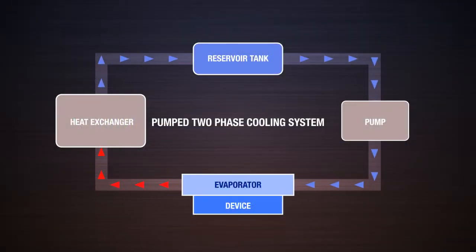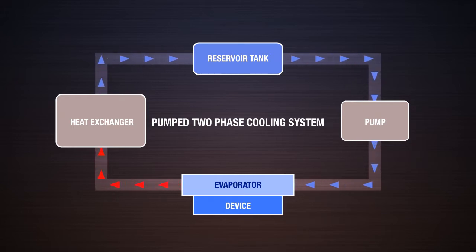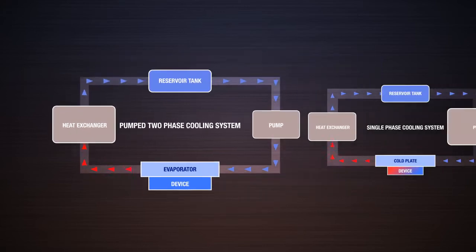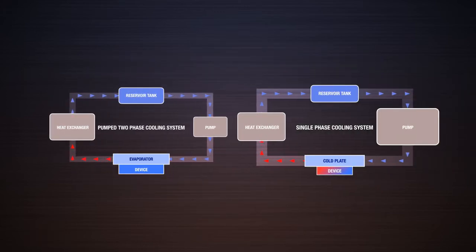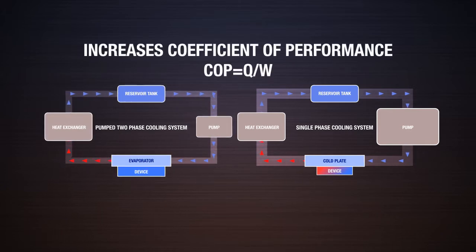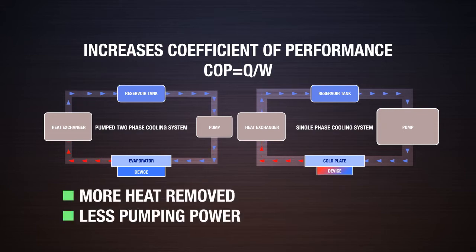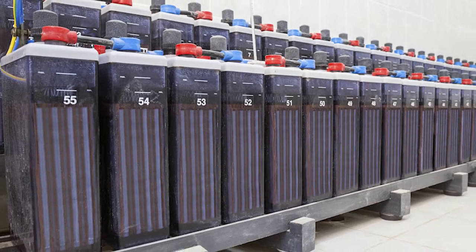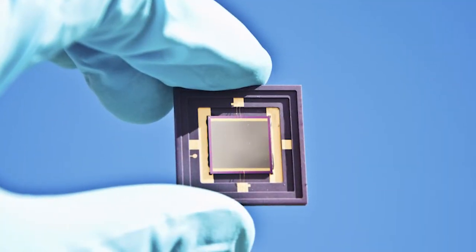Another key advantage of pumped two-phase or evaporative systems is they do not require high coolant flow rates. As a result, smaller pumps requiring less power and weight can be used to remove higher amounts of heat, in effect increasing the coefficient of performance, or COP, of the cooling system. This means more heat can be removed over a given surface with less pumping power.